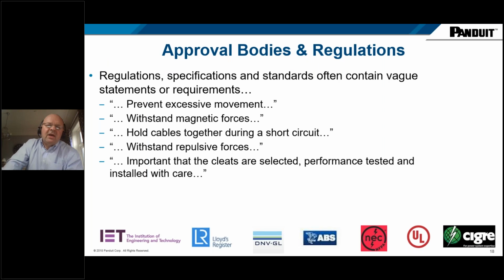So when we look at approval bodies or regulators, such as DNV, ABS, UL, they do give some guidance, and what they say is things that are fairly vague, such as when installing cable cleats, you should look to prevent excessive movement, to withstand repulsive forces or magnetic forces, and hold the cables together during a short circuit event.